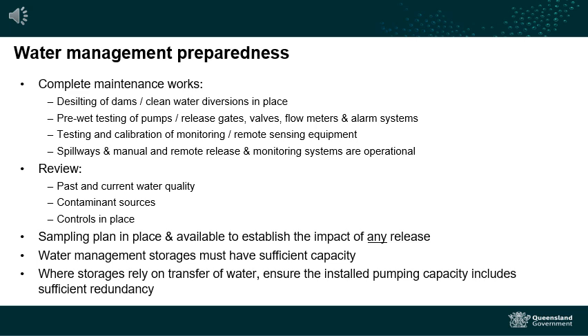Prior to the wet weather season, you should ensure there is adequate capacity in any water storage dams on your site. High rain events can also impact the integrity of dams. Therefore, maintenance works on-site dams and water storage facilities should be done ahead of any forecasted major rain event. Clean water diversion is key in managing site runoff. You should be minimising the volume of water that requires management ahead of each summer season and divert uncontaminated surface water from the site.